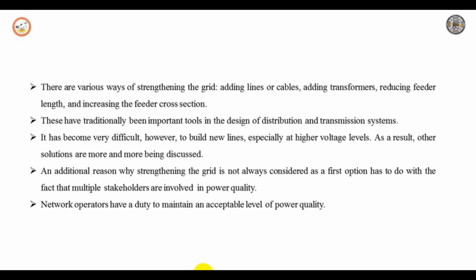There are various ways of strengthening the grid, like adding lines or cables, adding transformers, reducing the feeder length, and increasing the feeder cross sections. These have traditionally been an important tool in the design of distribution and transmission systems. It has become very difficult, however, to build a new line, especially at higher voltage levels. As a result, other solutions are more and more being discussed. There is an additional reason why strengthening the grid is not always considered as a first option.